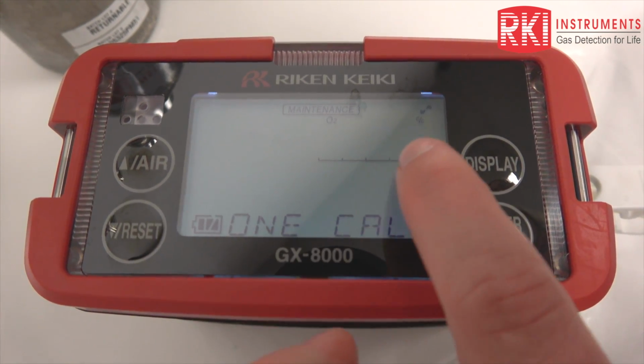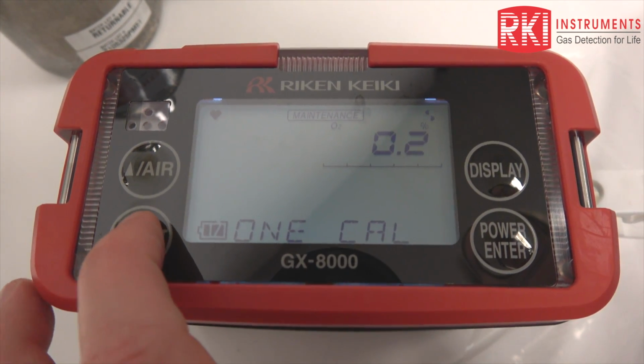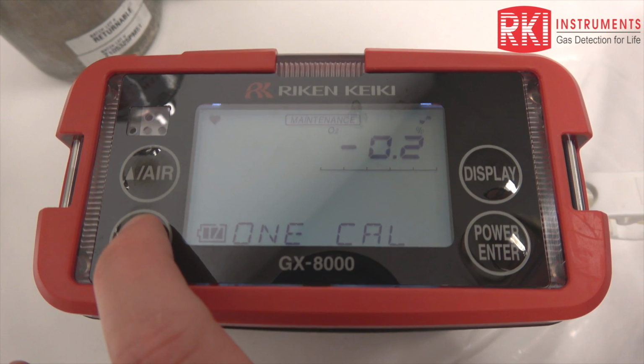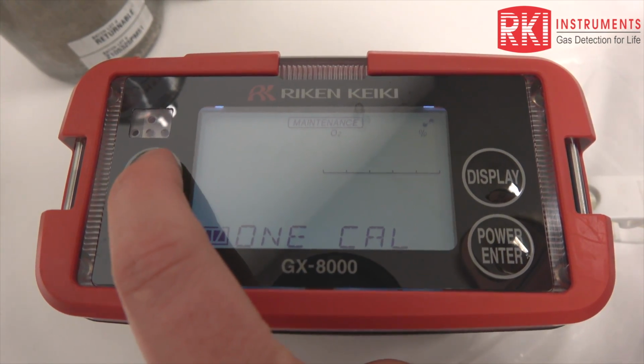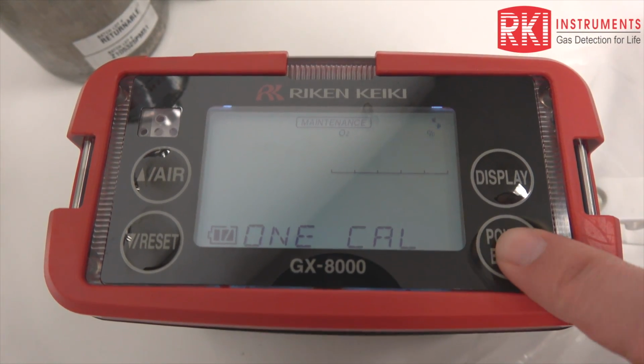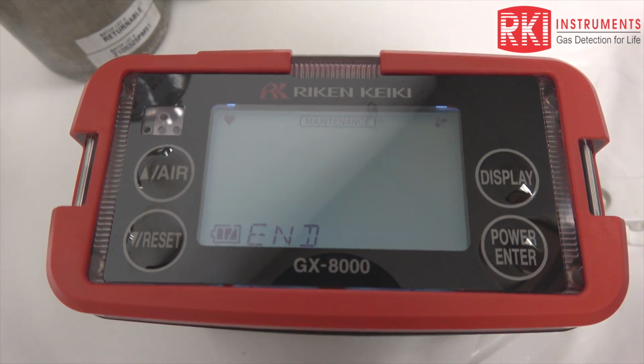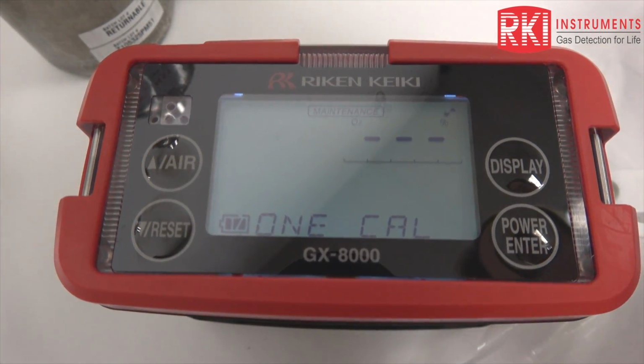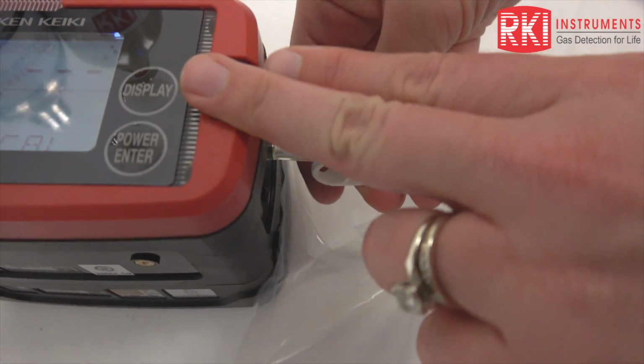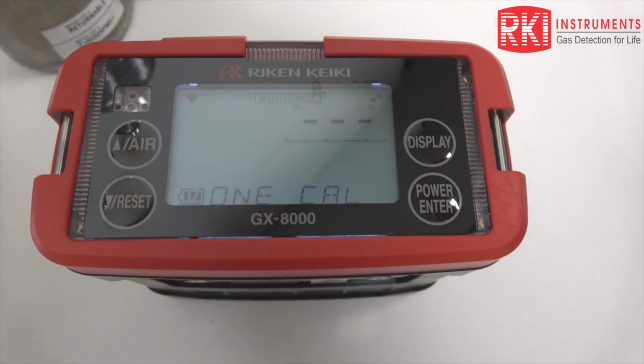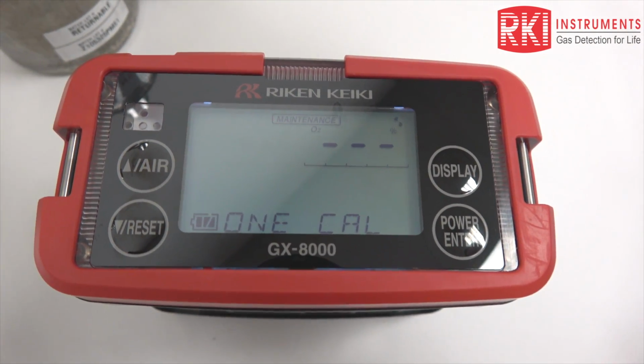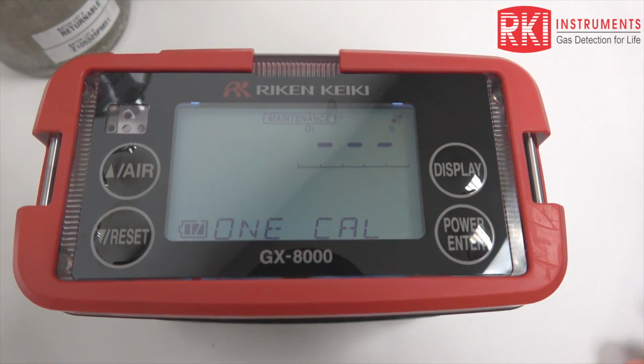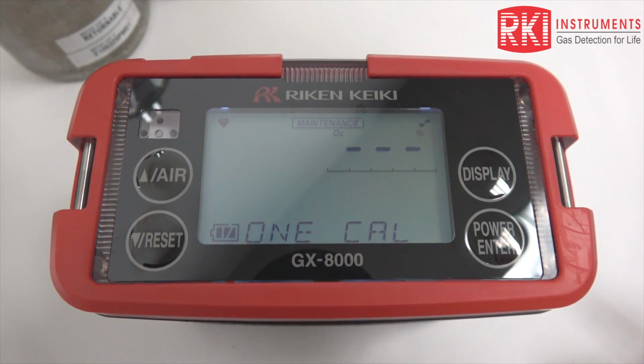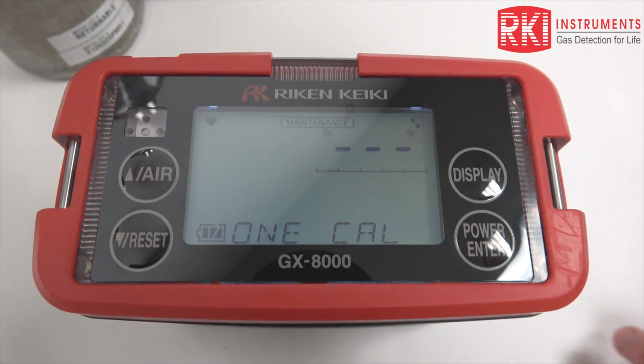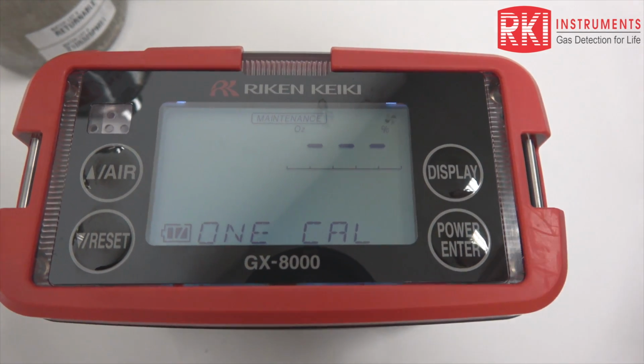let me see 0. So you can see this says positive 0.2, and if I use my down button, now it says minus 0.2. So this is about as close as I'm going to get to 0. I'm going to press power enter, and I'm done with my oxygen sensor calibration. I'm going to go ahead and just take my gas bag off. And now I'm going to calibrate the LEL combustible, the CO, and the H2S using a 4-gas mix that I have already put in a gas bag, so you don't have to watch me fill a gas bag again.